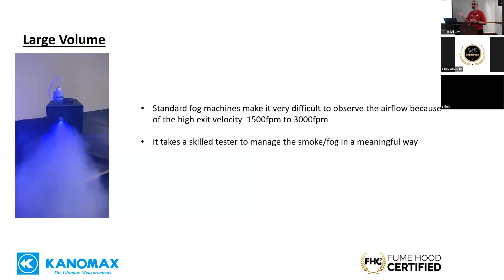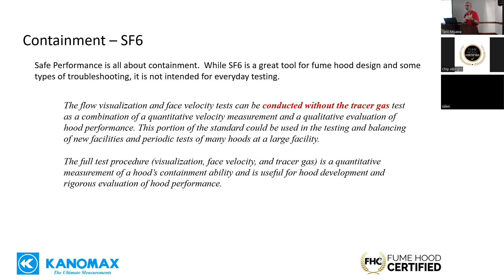And it's a very strong greenhouse gas. As a general rule, I think people would want to eliminate it from fume hood testing if they could. But this in italics underneath is right out of the ASHRAE 110 2016. And it says, flow visualization and face velocity test can be conducted without the tracer gas test. And what they basically say, if you read the whole thing, is that we shouldn't use SF6 for routine testing, that we should only use it for fume hood development and troubleshooting. So even ASHRAE 110, if you read every word in the standard, says some things that sometimes people are surprised about.